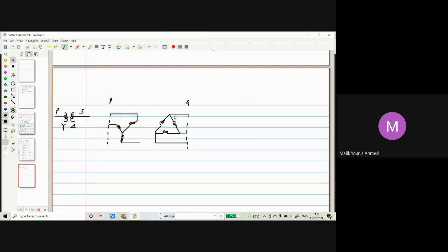So now let me draw the complete thing again. Here the series switch is open. Why? The winding is not star connected neutral grounded, the winding is star connected ungrounded. This is not grounded, so open. Now this will be impedance. Now moving to the shunt switch. The shunt switch will definitely be open here because shunt switches are closed only when the winding is delta, but the primary winding is not delta connected. So the shunt switch will be open, as well as the series switch.